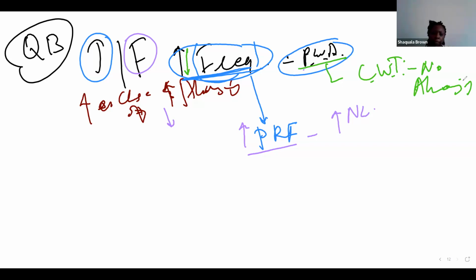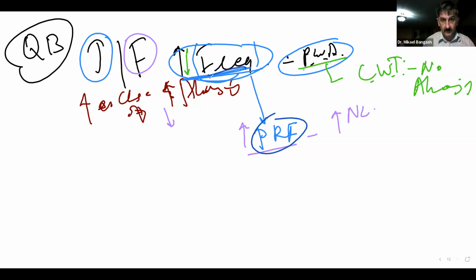Yes. Okay, so just be watchful. You can't say, Mike, but the answer for this question in the book was true. You gave it on the test, and now all of a sudden it's false. Well, it's false because maybe I changed the frequency to a PRF. Clear? Or it may become false because I changed the transducer, not a pulse wave transducer, it's a continuous wave transducer.